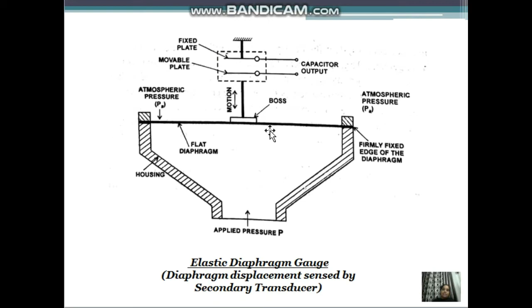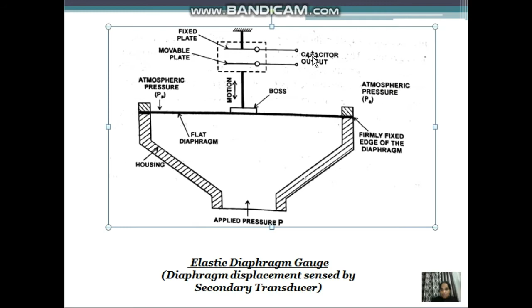We have discussed this already. This is called the secondary type of measurement. So this is how the elastic diaphragm gauge with a secondary transducer works. You already know the capacitance, C equals K into epsilon into A by D. If the distance between the two parallel plates decreases, its capacitance increases. Now the change in capacitance becomes the measure of the pressure if you calibrate it.